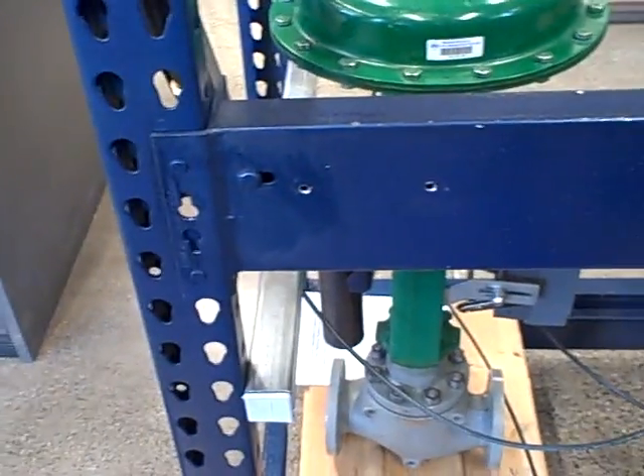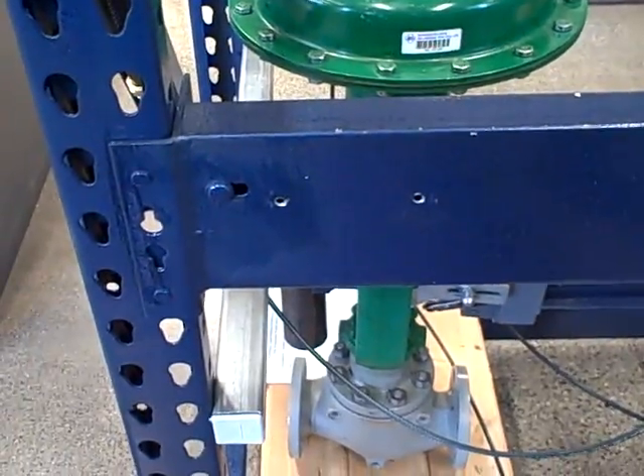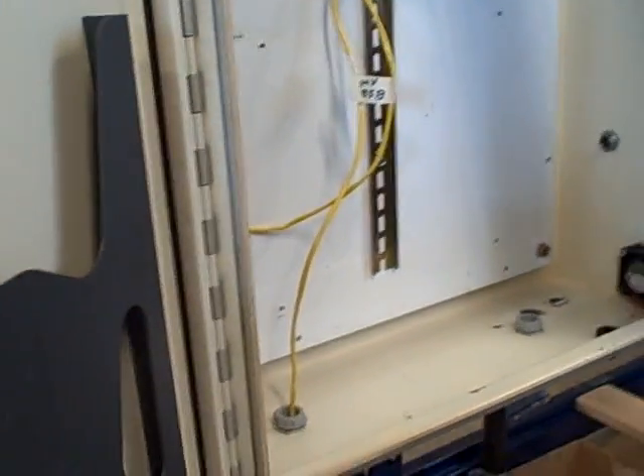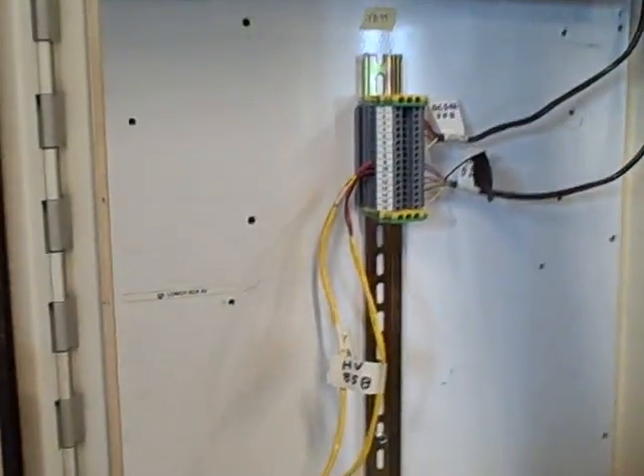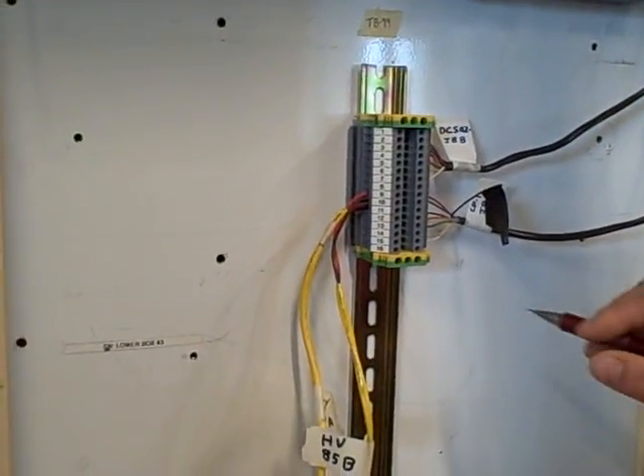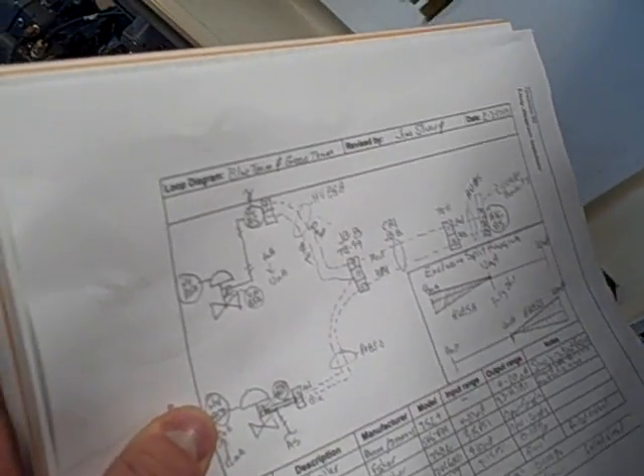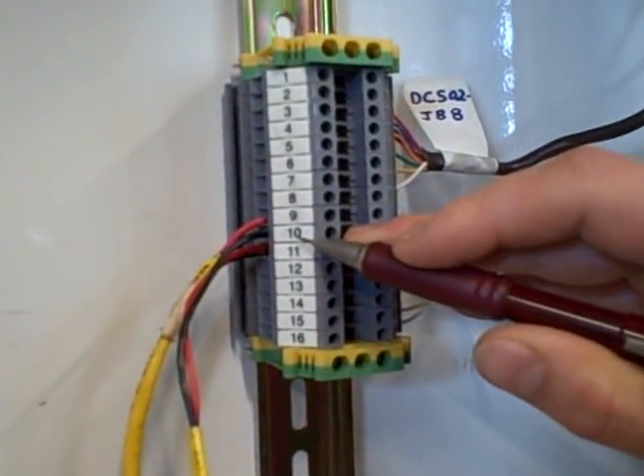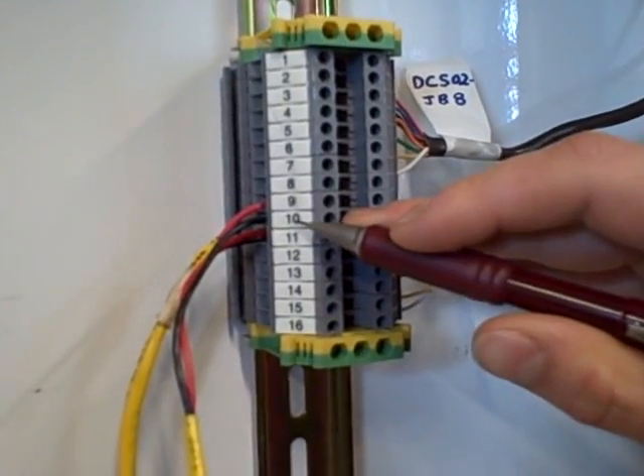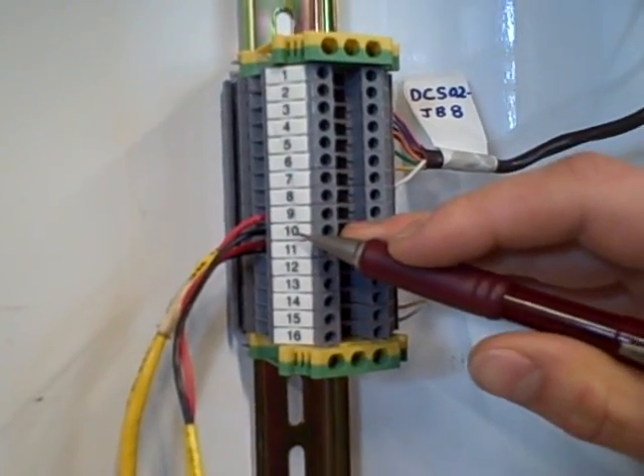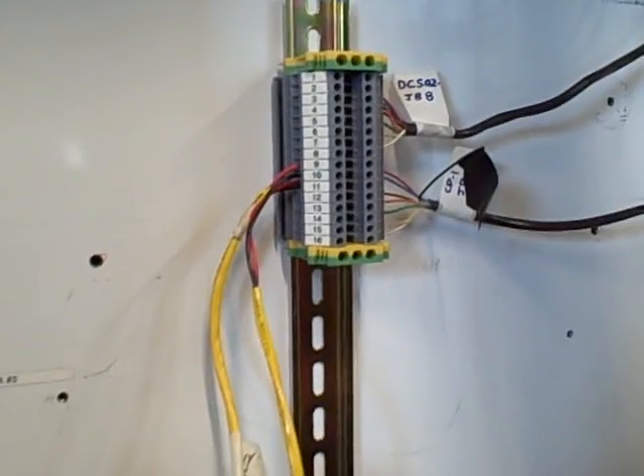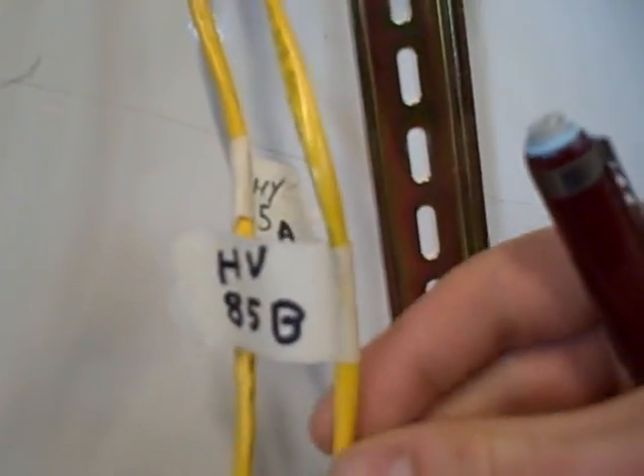Okay. Next person. Michael, let's go back to the junction box, JB8. At this point, we're going to follow the other cable. Okay, so we'll go back to junction box 8, and we find this 11 and 10, which would be the red to 11, and the black to 10, which would be the pair of cables that would be going to our other valve, HV85B.